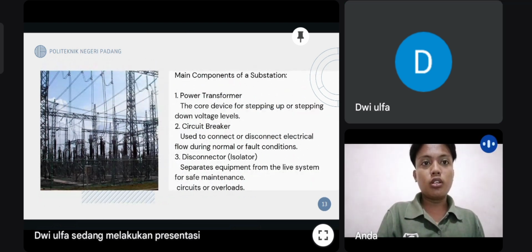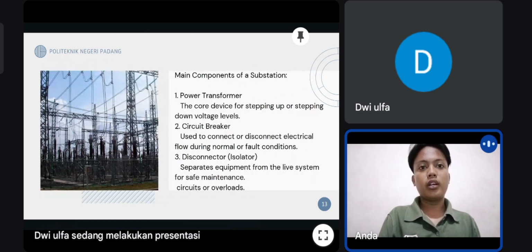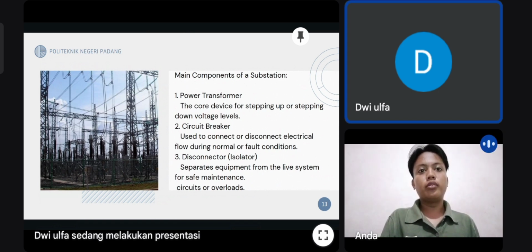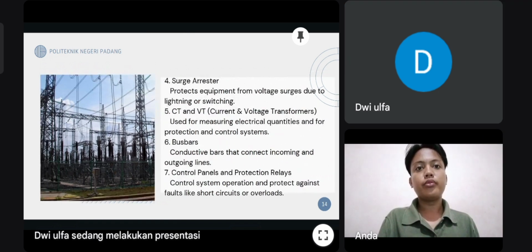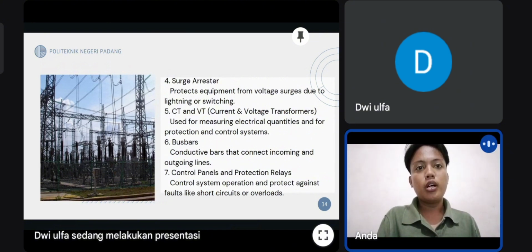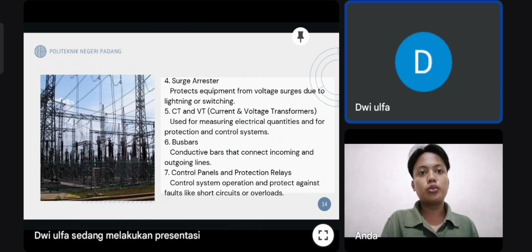Main components of a substation. One, power transformer, the core device for stepping up or stepping down voltage levels. Two, circuit breaker, used to connect or disconnect electrical flow during normal or fault conditions. Three, disconnector or isolator, which separates equipment from the live system for safe maintenance. Four, surge arrestor, which protects equipment from surges caused by lightning or switching.